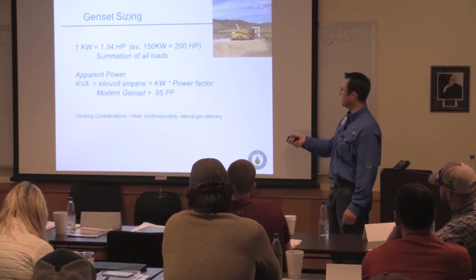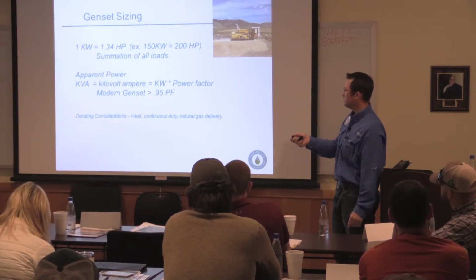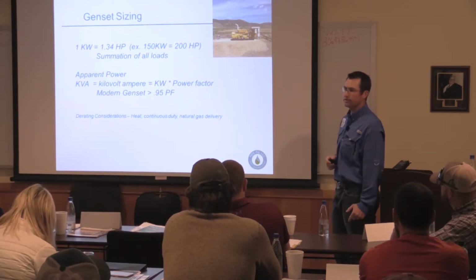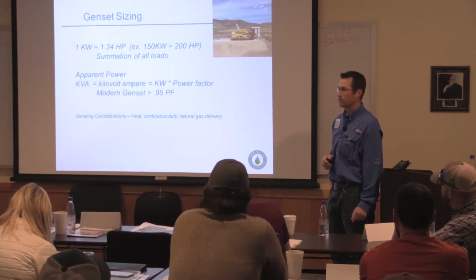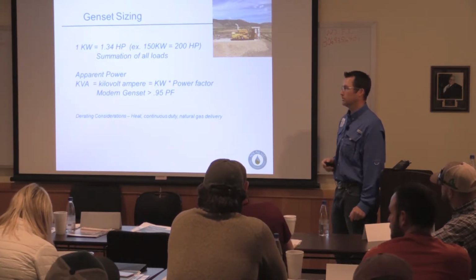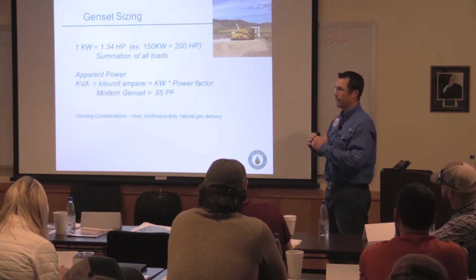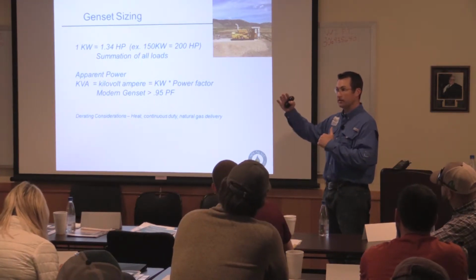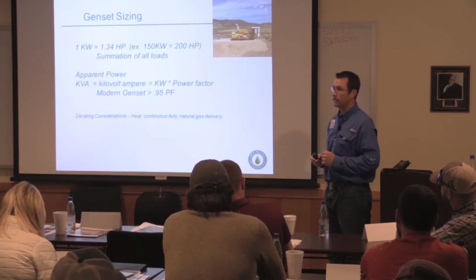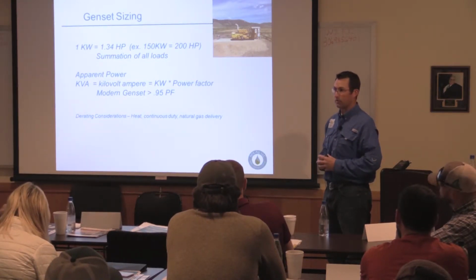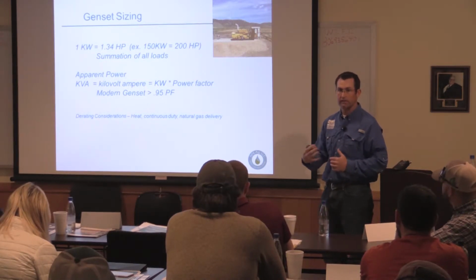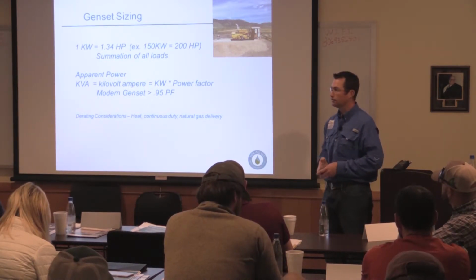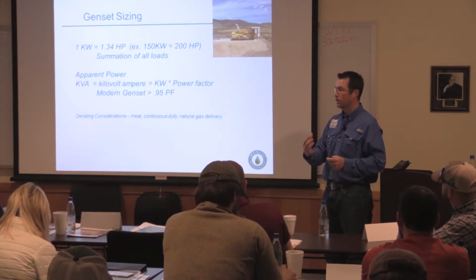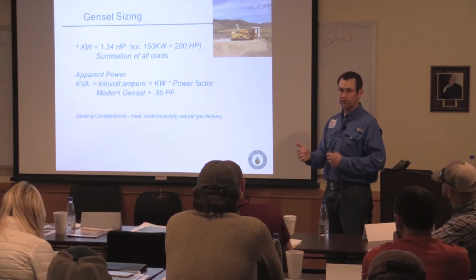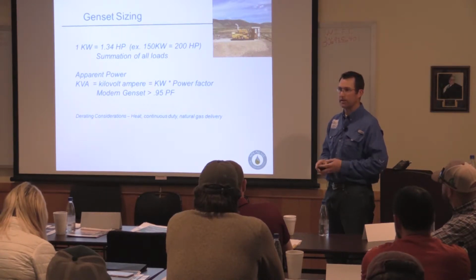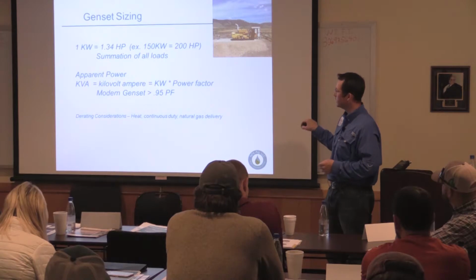Some other points on sizing: you must be oversized on your generator. There will be de-rates based on conditions, namely heat. Some of the gensets I've used, I've had to get into a 75% de-rate because of the tests I do in Arizona and the heat. It's horrible, it'll knock the power right down because heat affects not only the motor, since you've got less thermal efficiency pumping hot air through it, but also the electrical lines and motors that have to transmit and dissipate that heat.